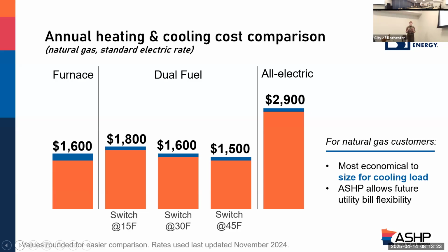That's a critical point with natural gas: even though you can't do really low switchover temperatures and save a ton on operational costs now, it's an investment in case natural gas prices spike or utility rates change. Having that flexibility to choose where your heat pump takes on the heating load helps maximize operational costs depending on the layout. Electricity tends to be stable over time with steady trends, but natural gas can be more volatile, so that choice and flexibility can be a really helpful selling point.